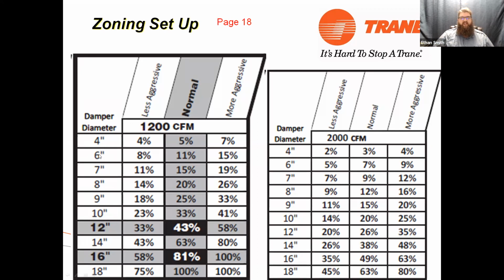So you can calculate this manually. It's not as precise. It doesn't accommodate your fittings. It's just educated guessing at that point. But if you didn't have room to put that static pressure sensor in, because I know they're out there, you can do it manually, and these charts are in the install manual.